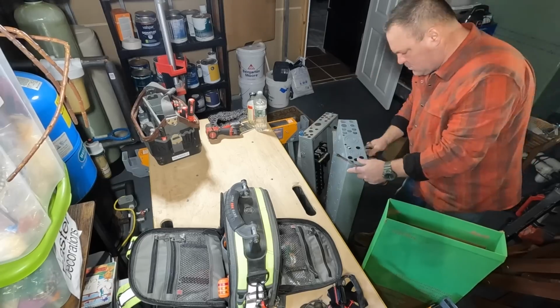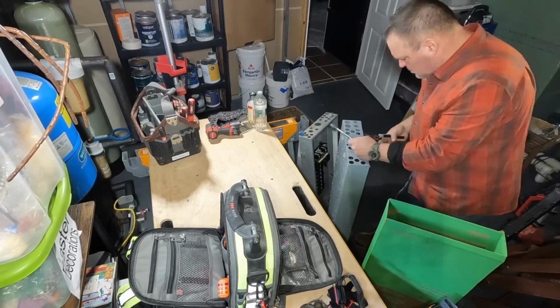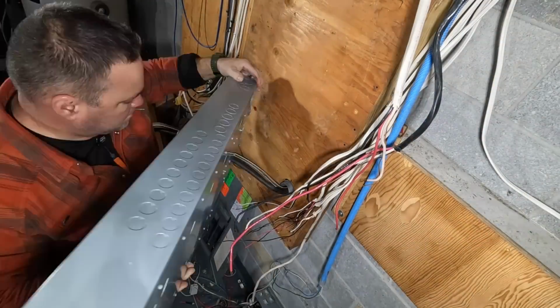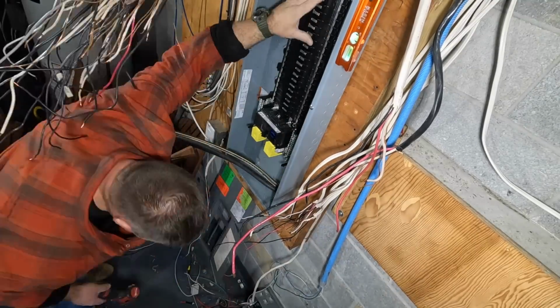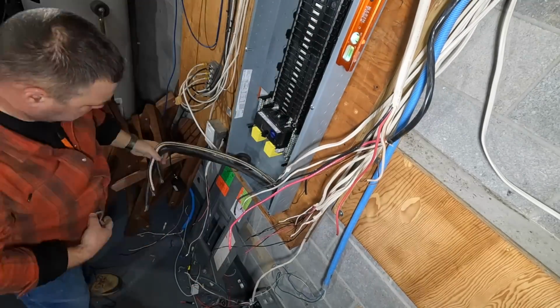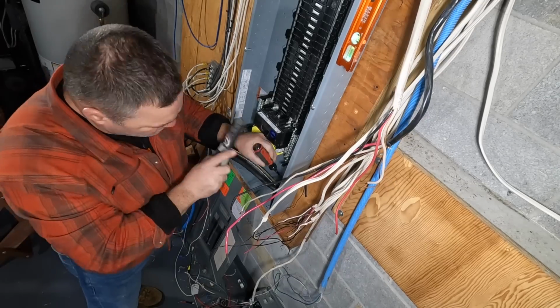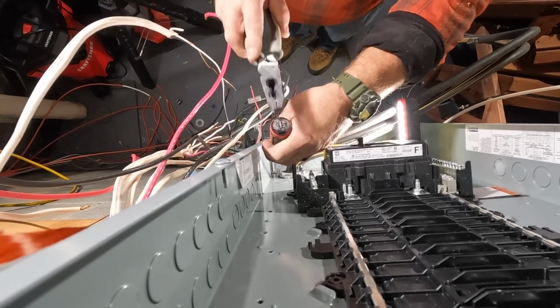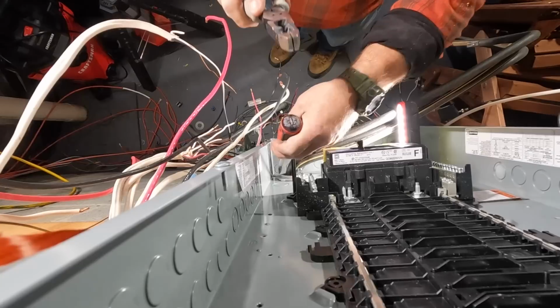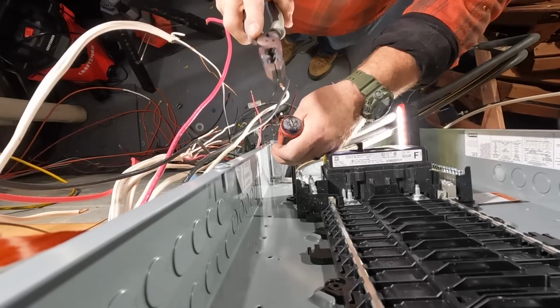But this panel was awfully large, so I decided to take out all of the knockouts at the top so I wouldn't have to do that once it's in place. Then I take the knockout out for the service entrance conductors and get that situated, screw it to the wall. Then I'm going to tighten up my lock nut and put on the bushing, and we're off and running to reattach all of the branch circuits.